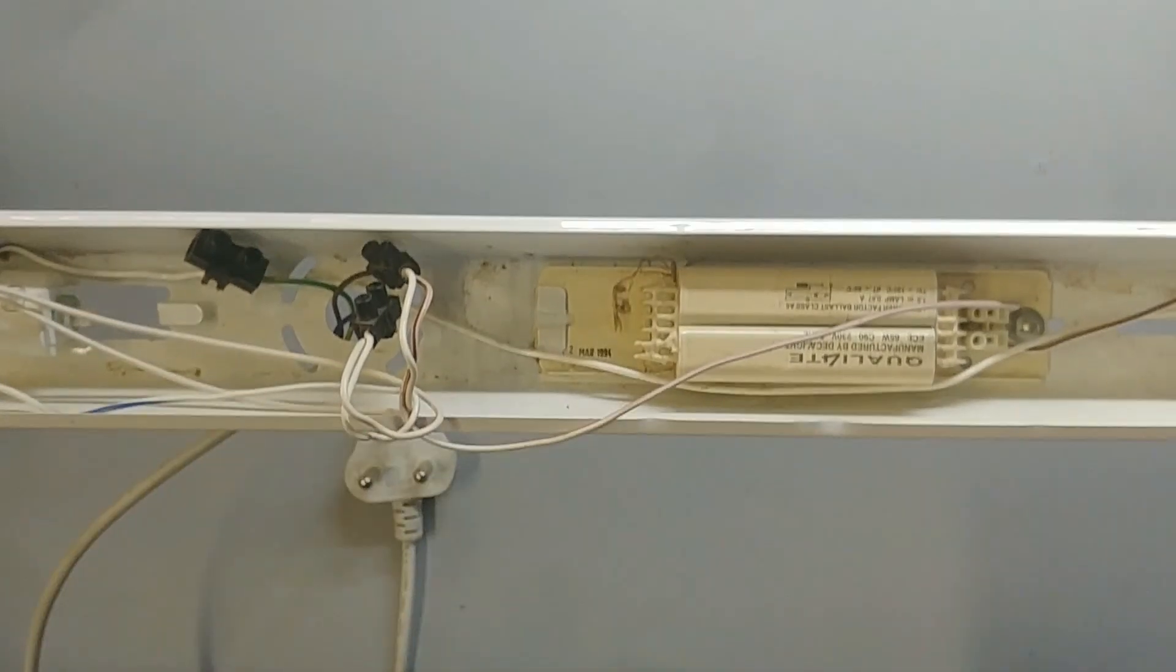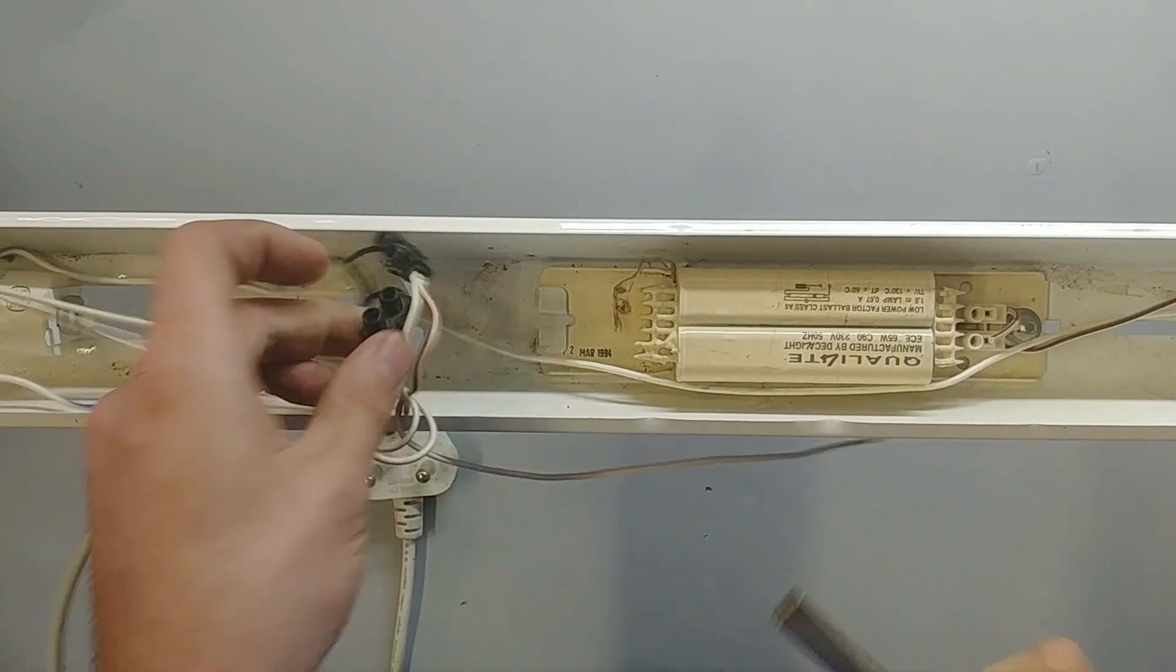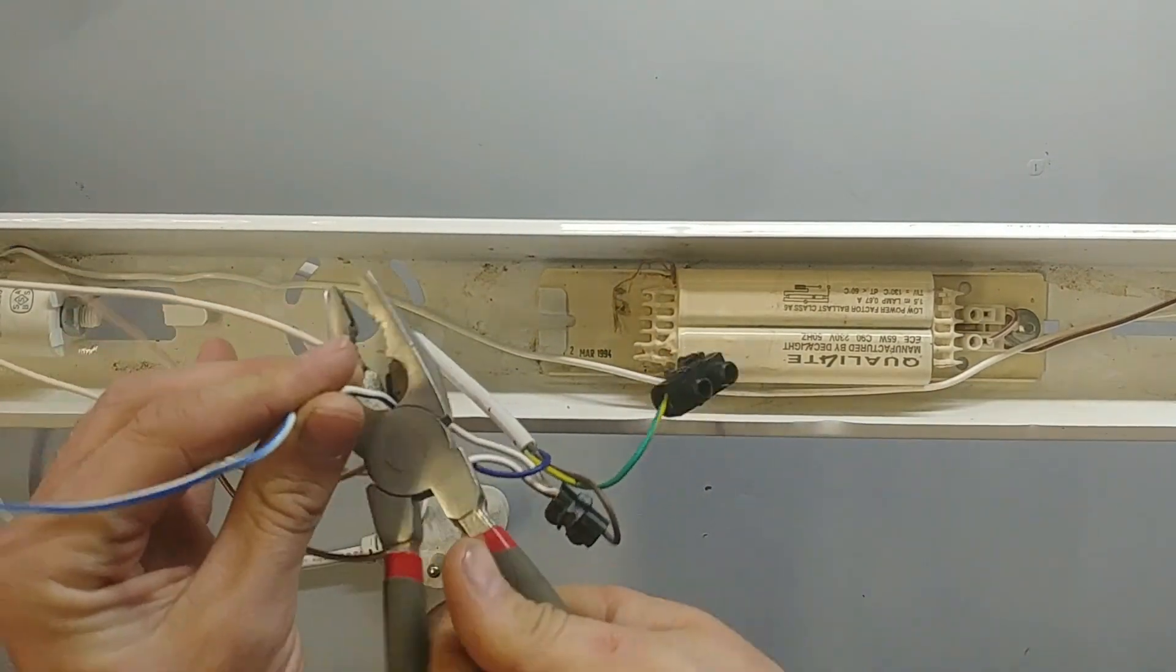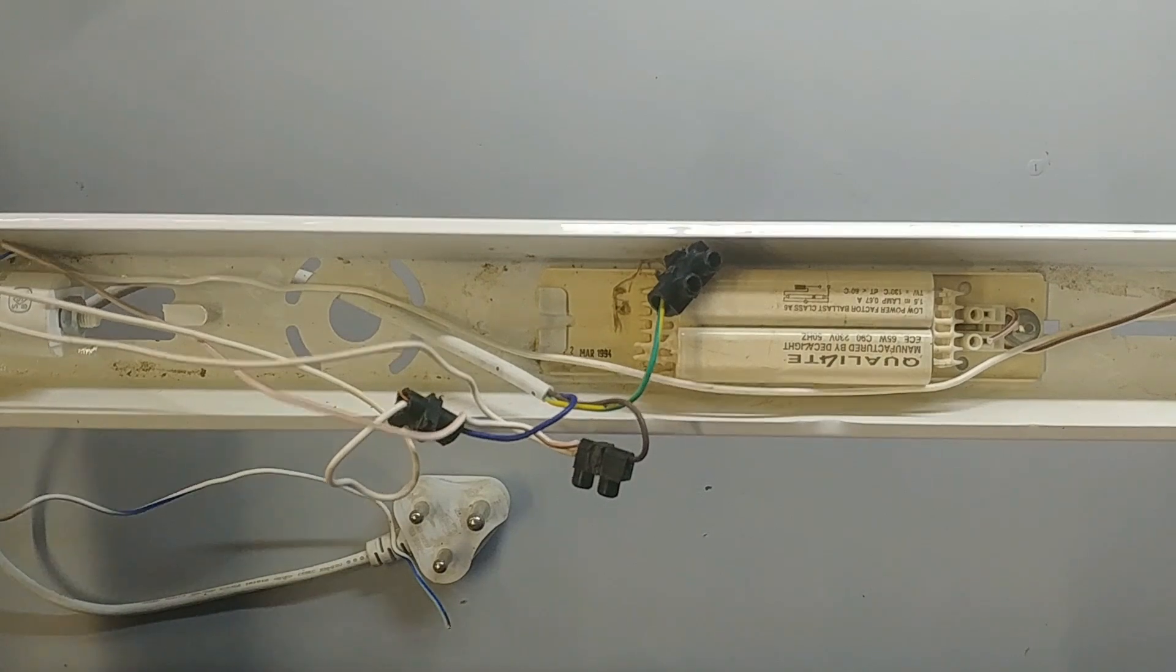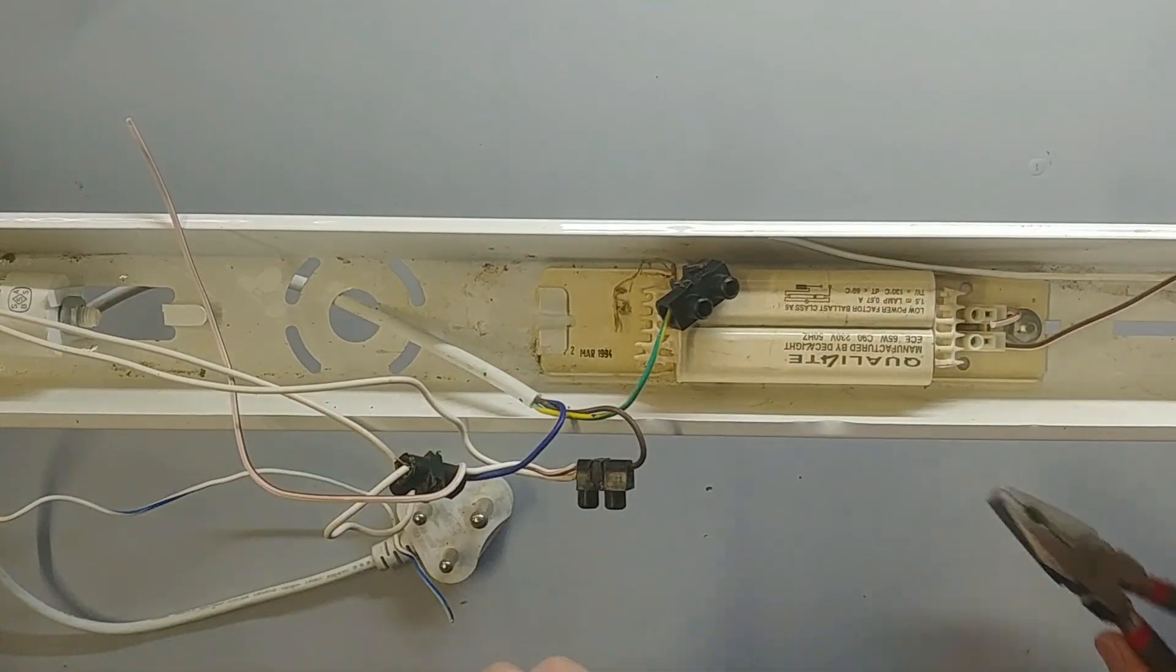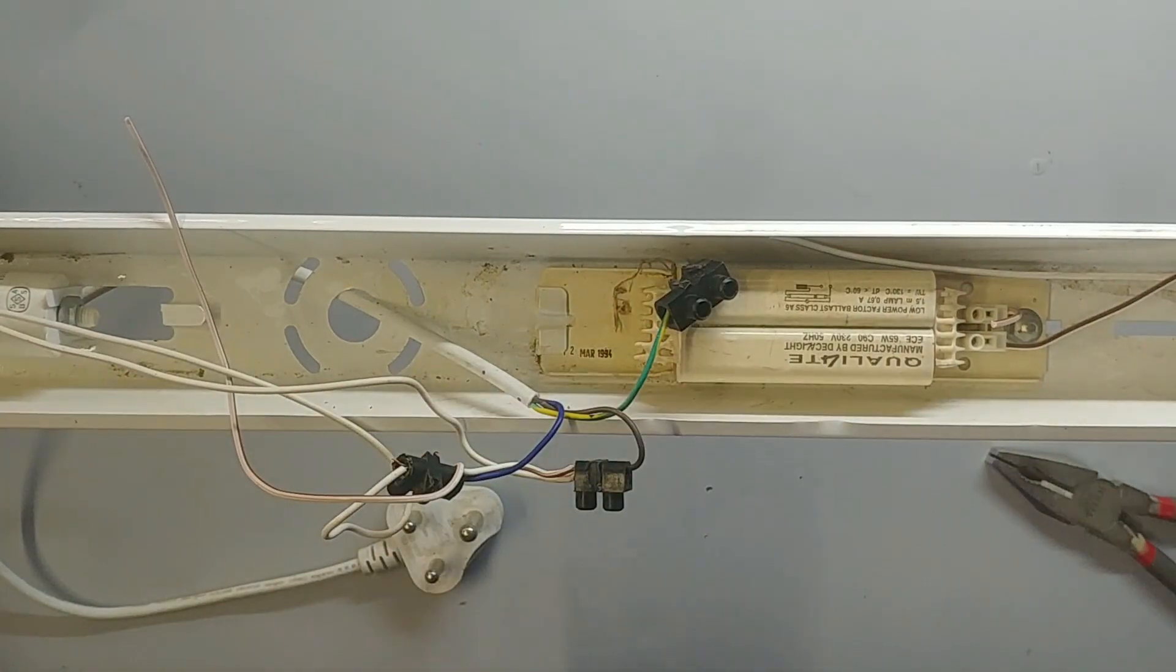And then this ballast can be removed. So I'm taking out these wires. The only wires I'm going to keep is the one coming from that side, coming to my neutral. Doesn't matter which way. And then this is the one that goes to the live. So these are the only two wires that I want to keep. I'm going to take all of this stuff out now.